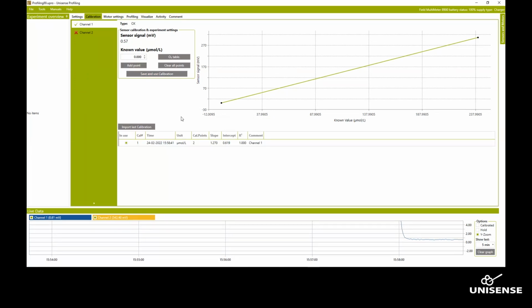Okay, and now the calibration appeared down here. Yeah, and you can see there are 2 calibration points, what the slope is and what the intercept is and what the R² value is. When you only have 2 points, the R² value is pretty close to 1 always. And the timing of it, so you can see later if you do other calibrations, then they will appear down there. I will remove now the calibration liquid and the cap as well.